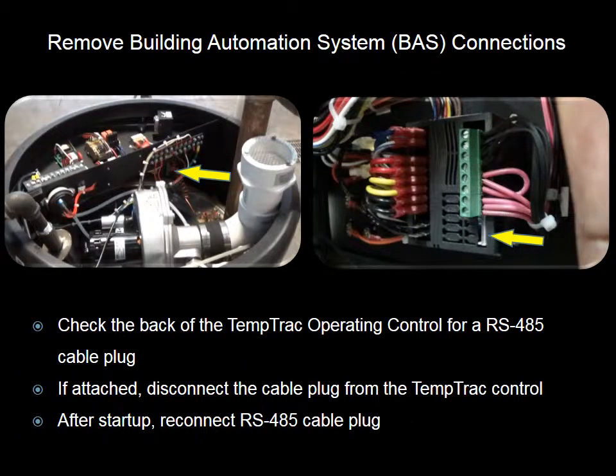Also check to see if a network type BAS connection is made to the Temptrac operating control. This is done by looking at the back of the Temptrac control to see if an RS-485 cable is plugged in. If so, remove the cable plug until startup of the water heater is complete. Remember to reconnect the cable plug after startup is complete.